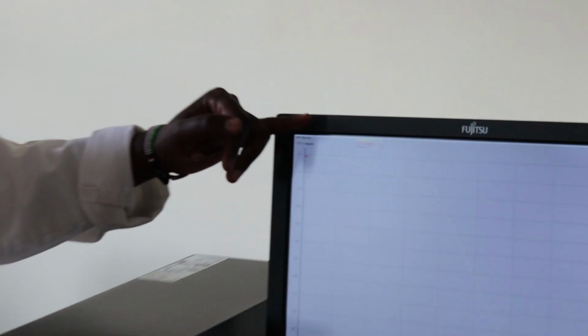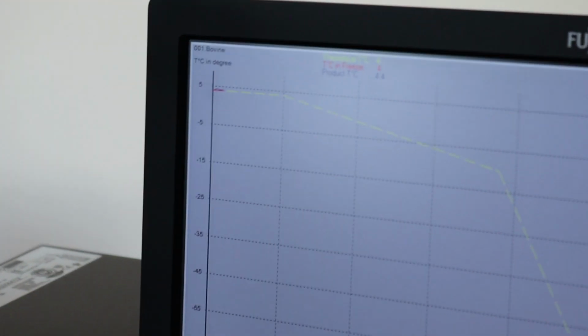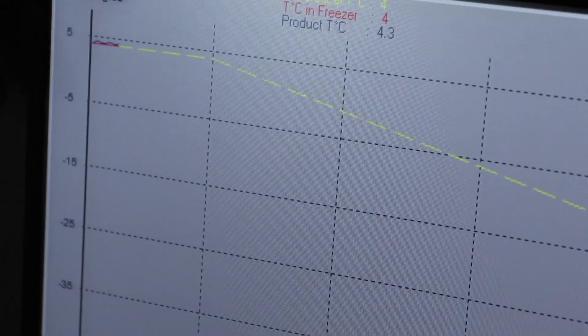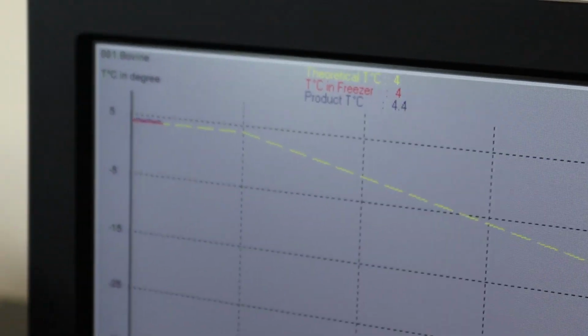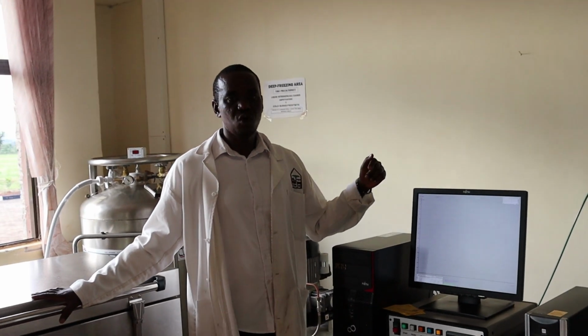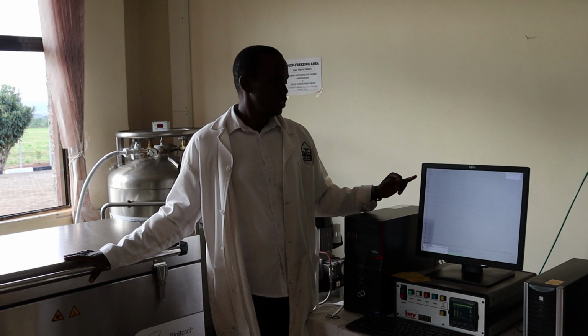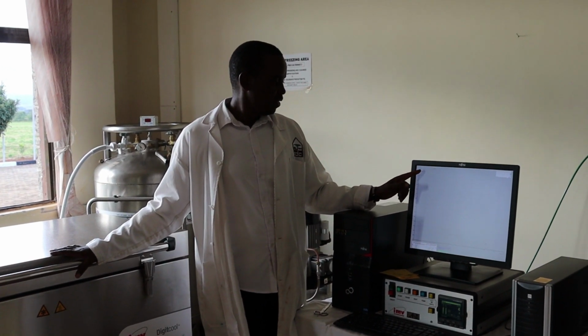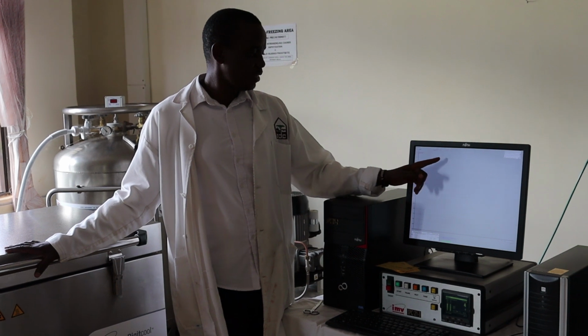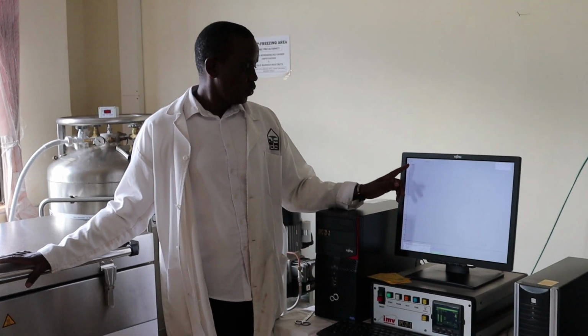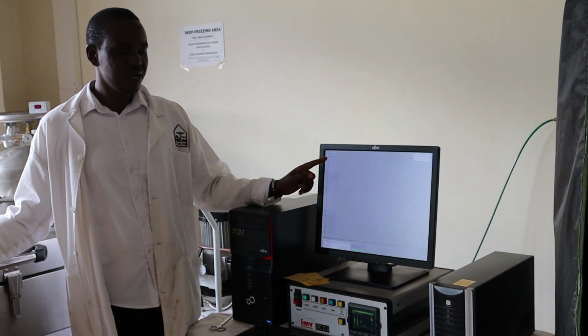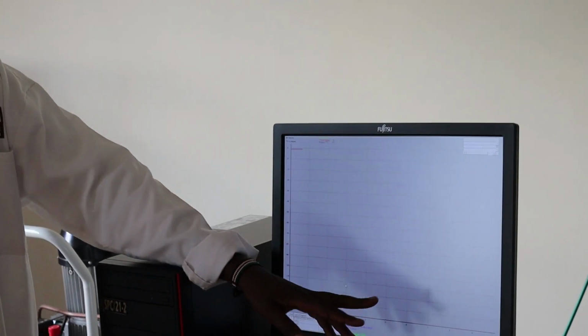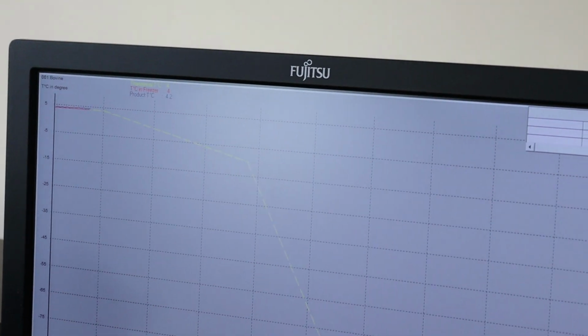So we have 3 curves. The theoretical temperature, the temperature of the chamber, and the product temperature. The product temperature basically means the temperature of the semen that is already inside the straw. So we expect 3 curves. The theoretical temperature is the one that guides us and is always in yellow. So then the red one and the black one should follow almost the same curve, all the way down to negative 145 degrees in a period of about 8 minutes.